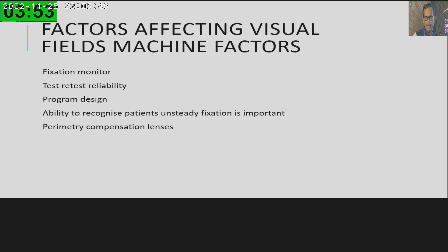Another very important area which is very often neglected is perimetry compensation lenses. What lens do you want to keep in that machine when the patient is doing the perimetry? Because the tasks are near. Patients are doing the test with progressive glasses, or with bifocals. All of that can add variables and artifacts to the perimetry. So ideally, if you are using the right compensation lens and seeing that there is no rim artifact, then that is a more ideal perimetry.